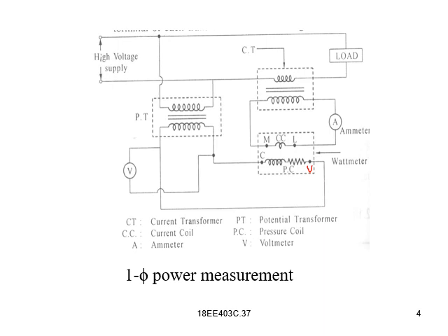You can also see that a voltmeter is connected across the PT secondary, and the CT is connected in series with the load. Its two terminals are connected, one to M and the other to L. In between there is an ammeter connected in series.